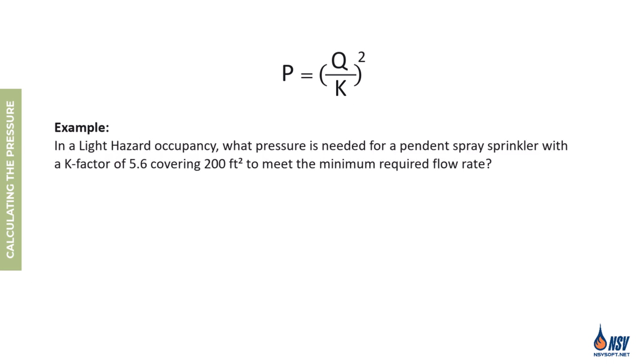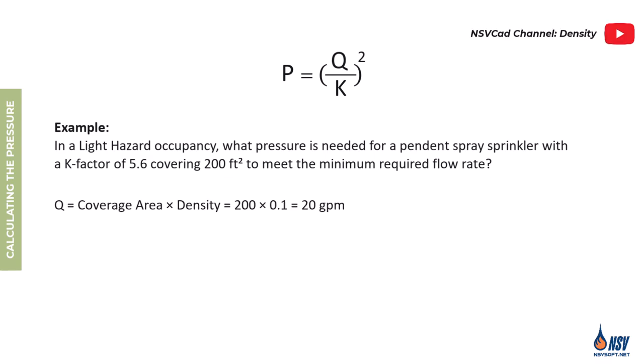For example, in a light hazard occupancy, if a pendant spray sprinkler with a K factor of 5.6 covers 200 square feet, what pressure is required to meet the minimum flow rate? We first multiply 200 by 0.1 to determine the required flow rate, which gives us 20 gallons per minute. Next we divide 20 by the K factor of 5.6 and square the result. The answer is 12.75 psi — the pressure needed to ensure the sprinkler delivers the required flow rate under the given conditions.